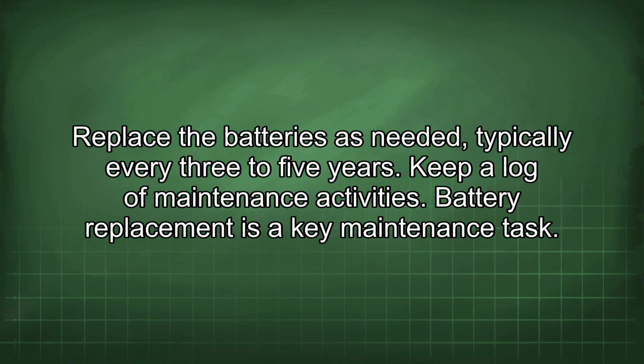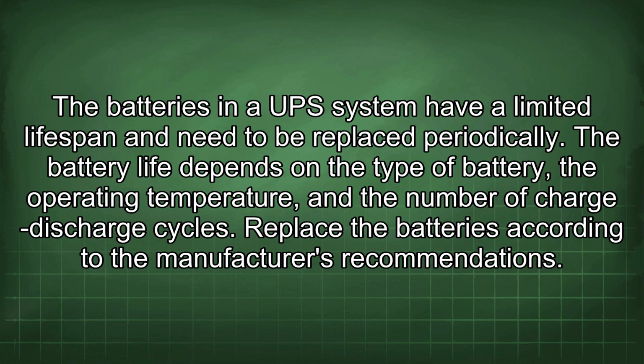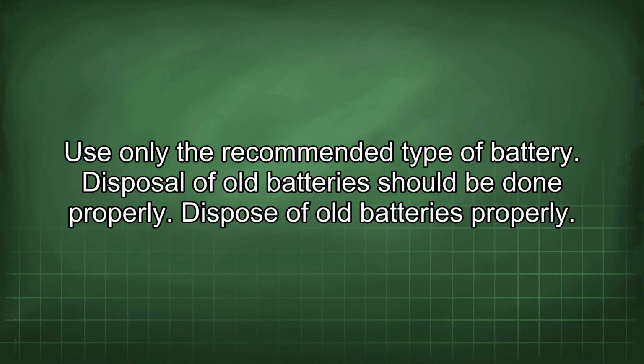Battery replacement is a key maintenance task. The batteries in a UPS system have a limited lifespan and need to be replaced periodically. The battery life depends on the type of battery, the operating temperature, and the number of charge-discharge cycles. Replace the batteries according to the manufacturer's recommendations. Use only the recommended type of battery.